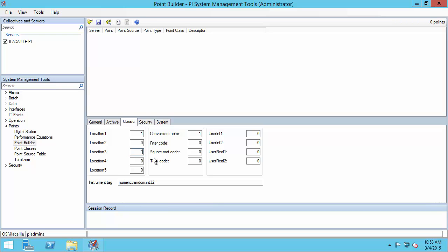If you wanted to create a polled or event point, you would choose Location 3 of 0. For an event point, you'd also have to go to the general tab and change the extended descriptor to identify what your trigger tag would be. If you need more information on the difference between advise, polled, and event points, check out the dedicated video and the PI Interface for OPC DA User Guide.